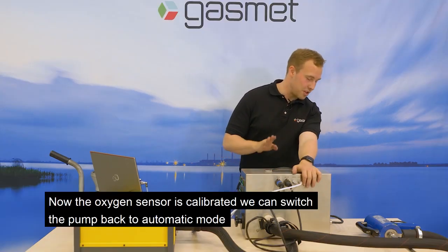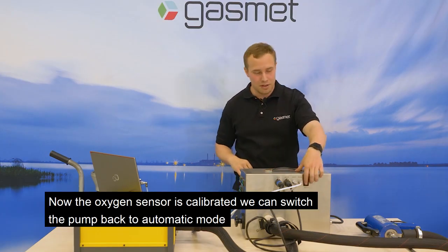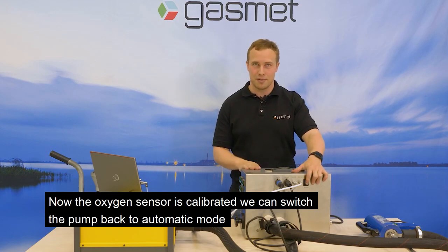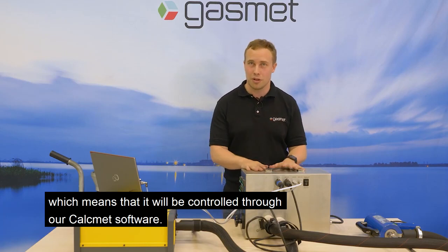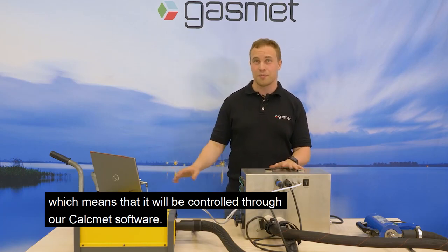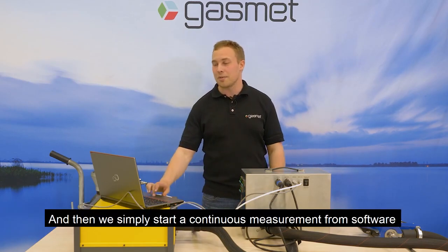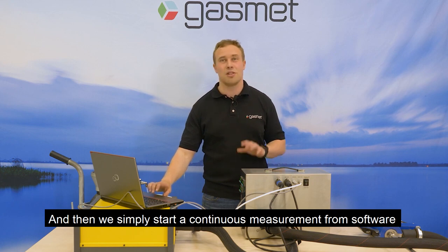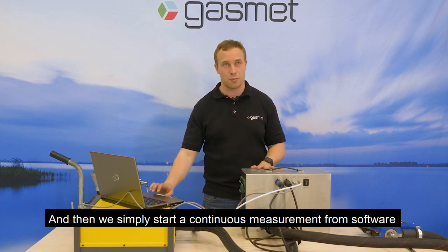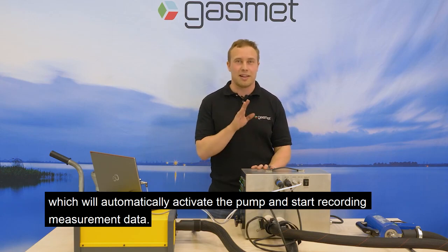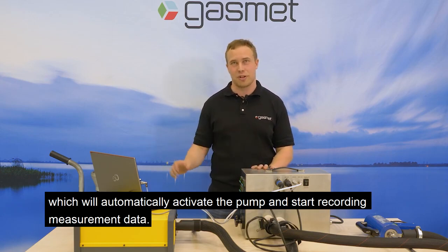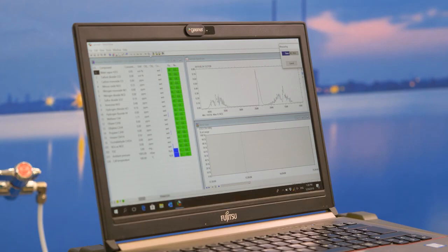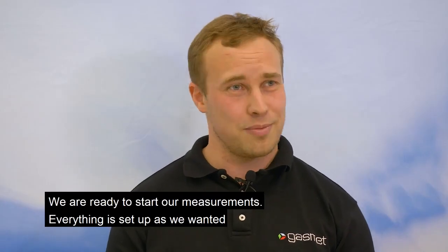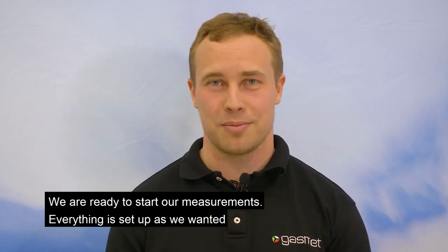Now the oxygen sensor is calibrated, we can switch the pump back to automatic mode, which means that it will be controlled through our CalcMet software. And then we simply start a continuous measurement from software, which will automatically activate the pump and start recording measurement data. We are ready to start our measurements. Everything is set up as we want it.